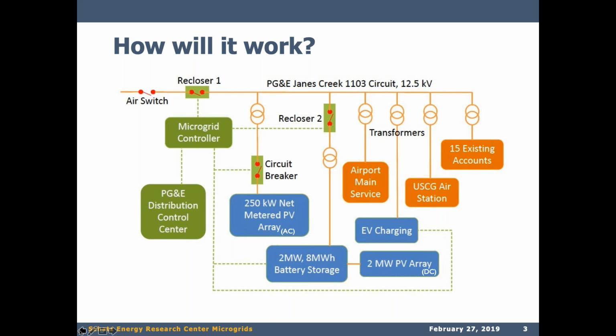The one other thing I'll point out is that when PG&E comes back online, the microgrid controller will sense that. It will synchronize the resources on the microgrid with the grid power, the frequency on the grid. When those are synced up, recloser 1 will close, and there'll be a seamless transition back to being parallel with the grid. The battery and PV system, the 2 megawatt system, will go back into grid following mode. It was in grid forming mode during the island situation. The PG&E distribution control center block just shows that there will be insight to the microgrid and control capabilities from PG&E's distribution control center, and I'll say a little bit more about that in a moment.